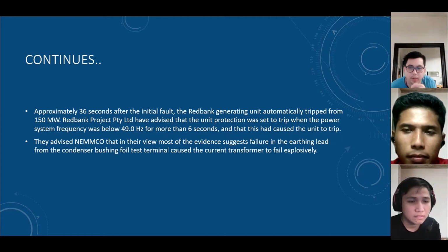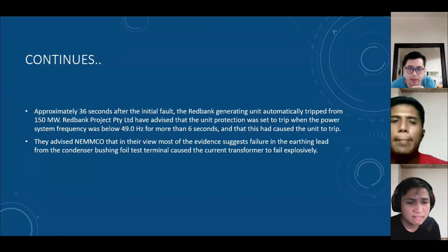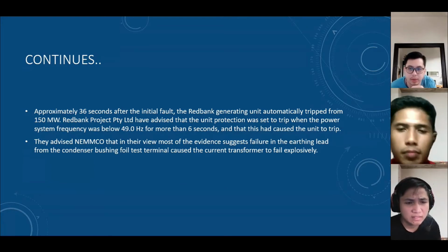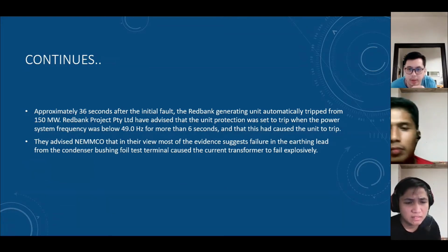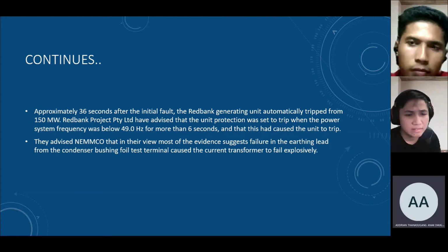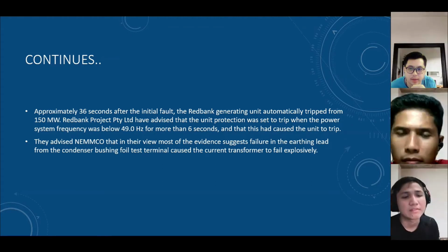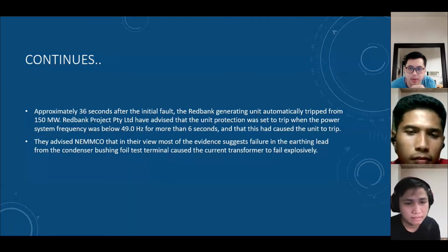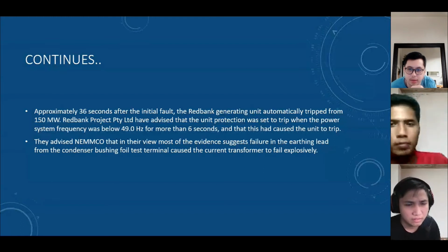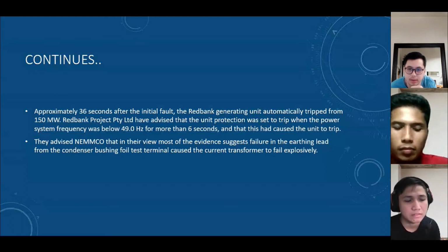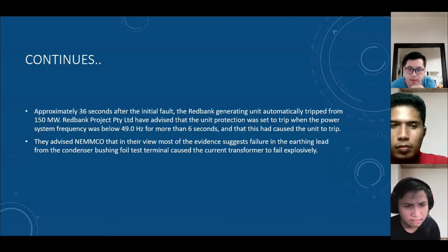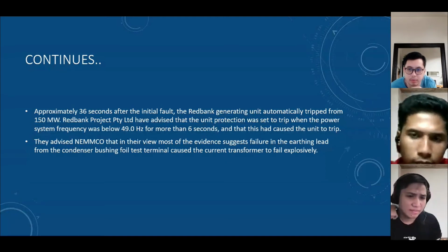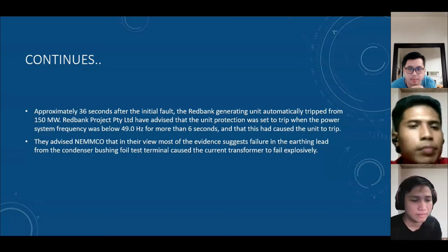Okay, approximately 36 seconds after the initial fault, the Redbank generating unit automatically tripped from 150 megawatts. The Redbank project advised that the unit protection was set to trip when the power system frequency was below 49 hertz for more than 6 seconds, and this caused the unit to trip. NEMMCO also advised that most of the evidence suggested the failure was in the earthing lead from the condenser bushing foil test terminal, which caused the current transformer to fail explosively. Next.